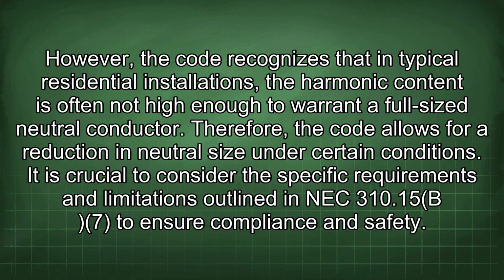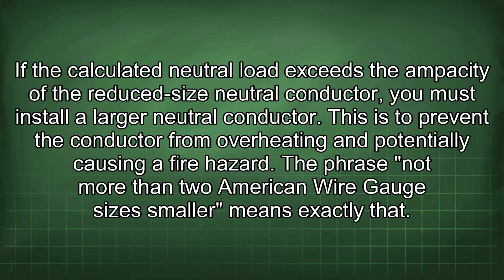It is crucial to consider the specific requirements and limitations outlined in NEC 310.15(B)(7) to ensure compliance and safety. If the calculated neutral load exceeds the ampacity of the reduced size neutral conductor, you must install a larger neutral conductor. This is to prevent the conductor from overheating and potentially causing a fire hazard.